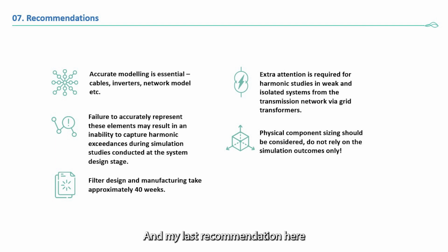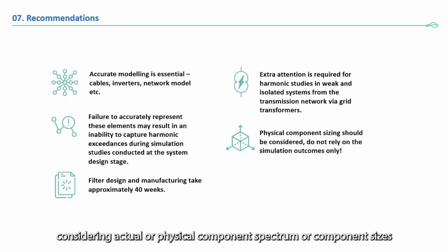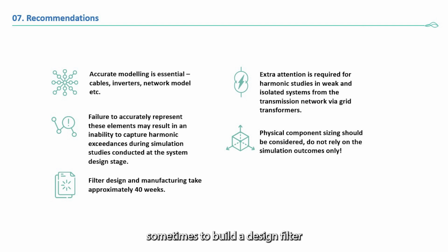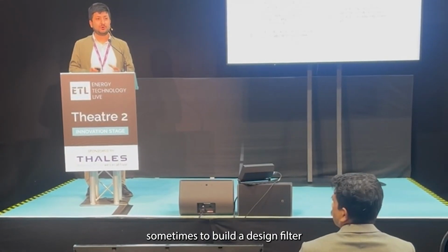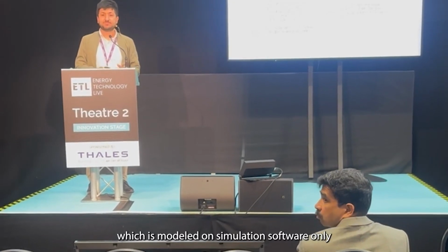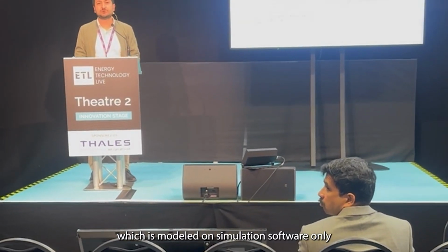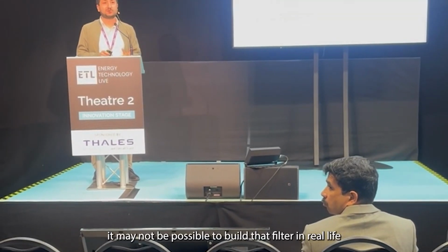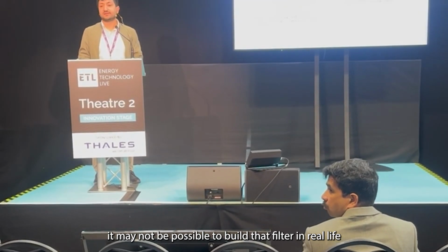And my last recommendation here, to design a harmonic filter, we shouldn't rely on software simulations only. We should design harmonic filters considering actual or physical component spectrums or component sizes. Sometimes a filter designed in model or simulation software only may not be possible to build in real life.